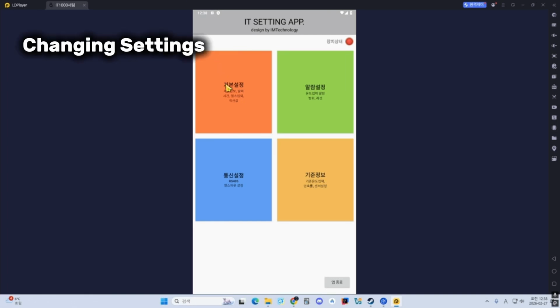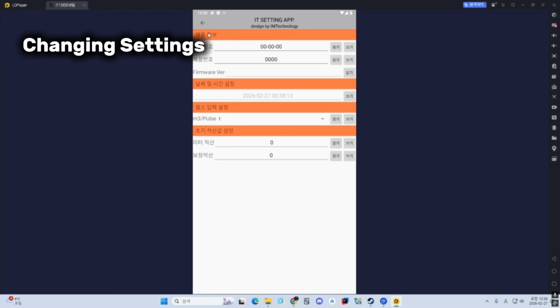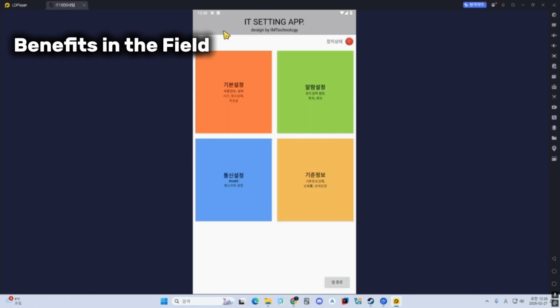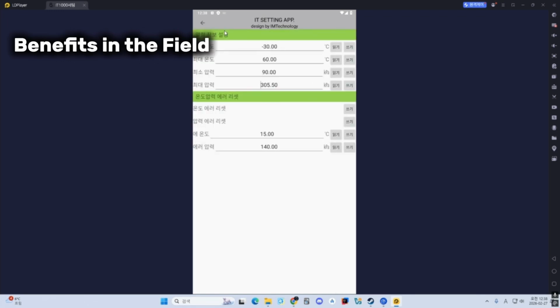In the basic settings menu, you can check the lot number, date, time, and pulse input values. Simply tap Read to load the current values, enter your changes, and tap write to apply them to the device immediately. With this app, you can calibrate errors or set up communication environments on site without a laptop. This significantly reduces your work time.